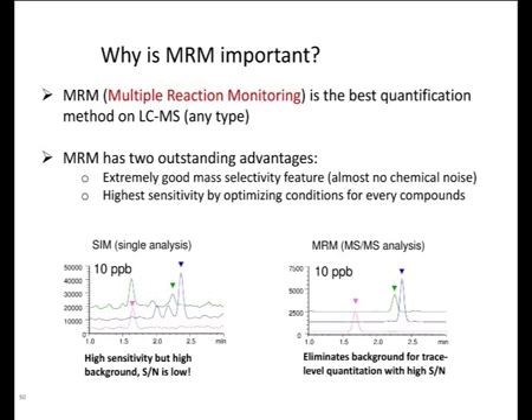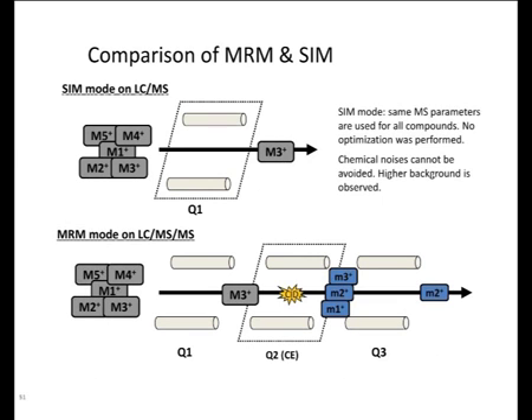Now the transition is that 500 gives 300. Because of this specific transition, you get very good selectivity, very less noise, and the signal-to-noise ratio will improve. Therefore, MRM is a good quantitative tool for the quantitation of compounds like peptides from a complex matrix. This is a comparison of MRM and SIM. In SIM you are monitoring only a single line. In MRM you are monitoring the transition, precursor to product.